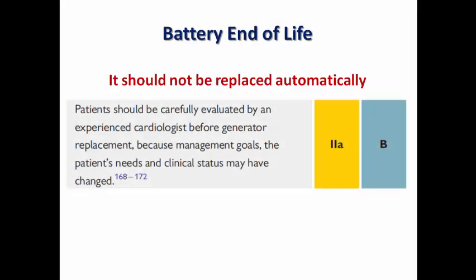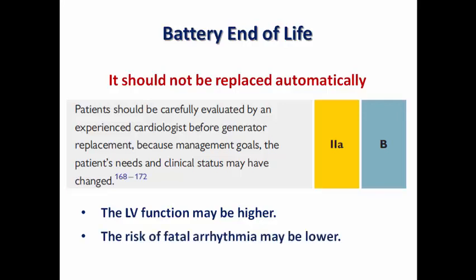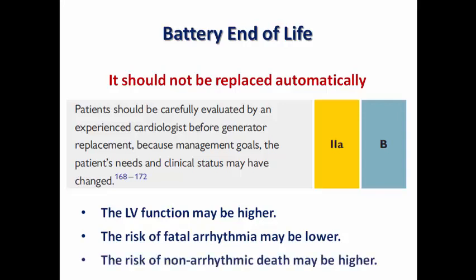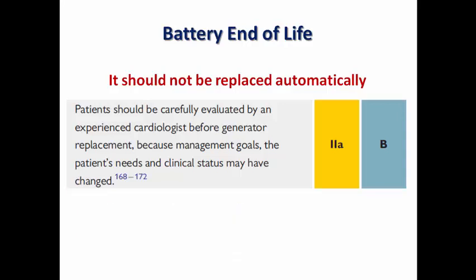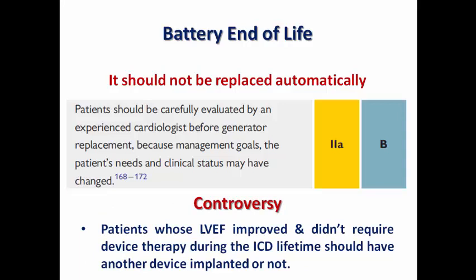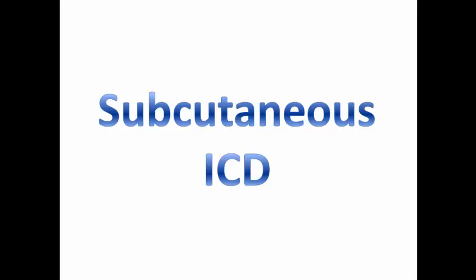Unlike a conventional pacemaker, an ICD approaching battery end-of-life should not be replaced automatically. The patient should be carefully evaluated by an experienced cardiologist, as management goals, patient needs, and clinical status may have changed. For example, LV function may be higher than before, the risk of fatal arrhythmia may be lower if no therapy was delivered during the entire ICD lifetime, or the risk of non-arrhythmic death may be higher due to severe advanced heart failure or non-cardiac comorbidities. There is currently no clear recommendation for patients with improved LV ejection fraction who received no ICD therapies.